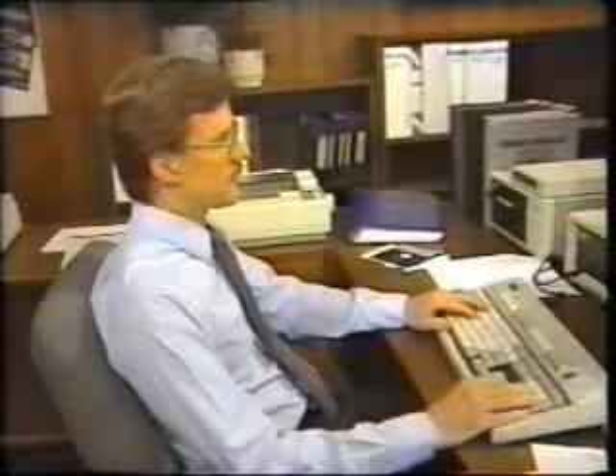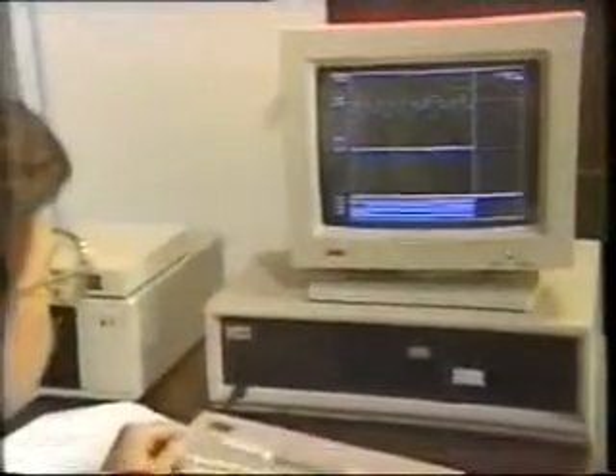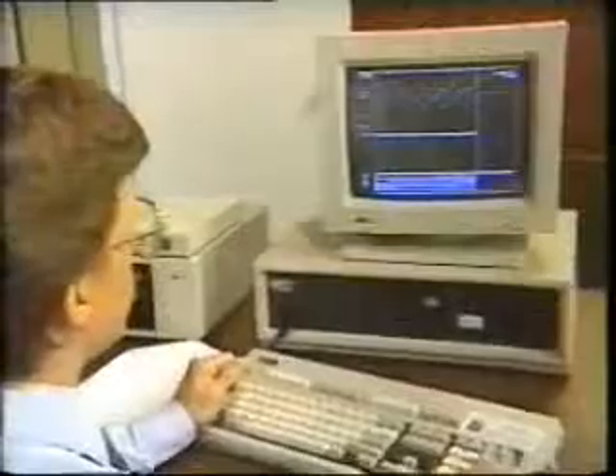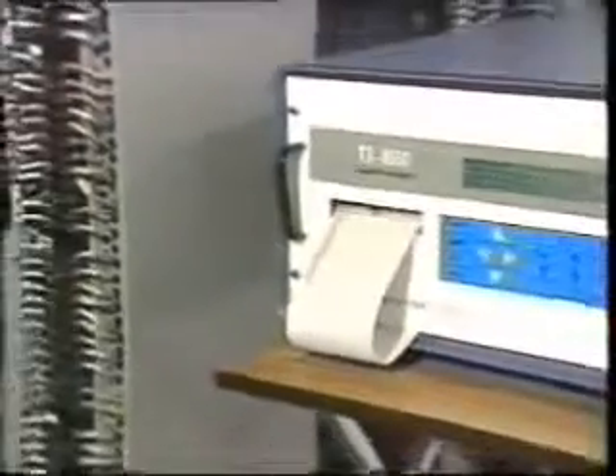A distinctive advantage is the capability for immediate remote retrieval. Information from various locations can be brought into a master computer for analysis at a central location. In this context, another advantage is in the precise timekeeping of the digital system. Yet another advantage is the capability to adjust the individual trigger set points from remote central control. In some digital systems, a printout of equipment status can be produced similar to the SER. As further development takes place, it is probable that gathered information will be analyzed instantaneously by the computer and switching operations initiated. Keep your eye open for such developments on your power system.